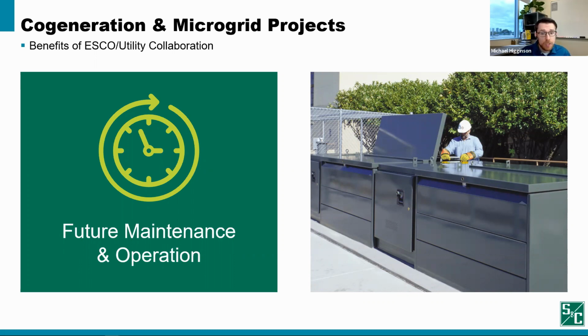Utility operations may also be impacted by the presence of a locally islanding system. Specifically, it's common that we de-energize electrical power equipment before working on it. Electricity can be dangerous, and de-energization of equipment can make work safer. If there is a system that can island and keep equipment energized after the utility has been disconnected, it's important that utility personnel understand this and are aware of how it's going to work.